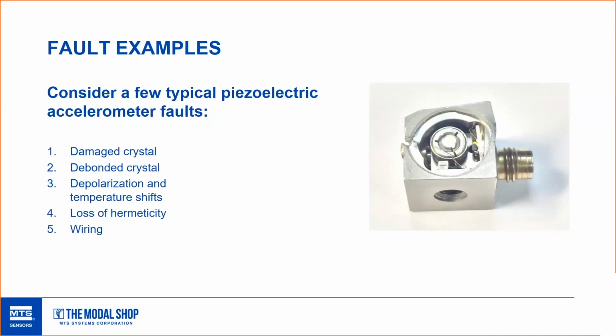And wiring. Wiring can go bad from shock or over time. It can cause complete sensor faults or intermittencies. It could be amplitude-based. This could be within the sensor itself or externally. And we all know intermittencies are some of the most challenging things that we can face as far as sensor faults. It can be infuriating. But again, think to yourself, would a handheld calibrator catch this? Maybe, maybe not.